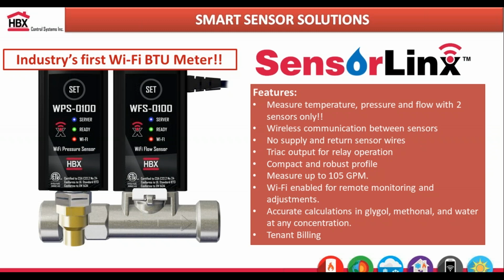The big thing with the SensorLinx sensors is that there's wireless communication between your return and supply sensors. There are a lot of standards coming out in the US and Canada in terms of how you can use thermal meters for billing purposes. A lot of these manufacturers come from Europe, and a typical BTU meter comes with a main hub controller with 2 temperature probes. You're limited on distance, where the maximum distance of these sensors is typically about 2 meters, and you can't cut or splice these sensors because it affects the resistance.